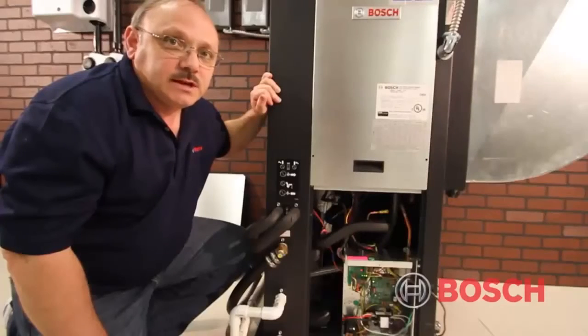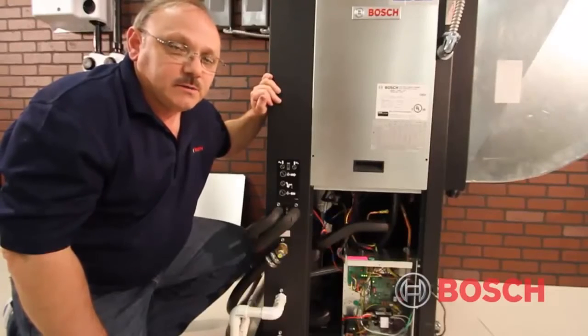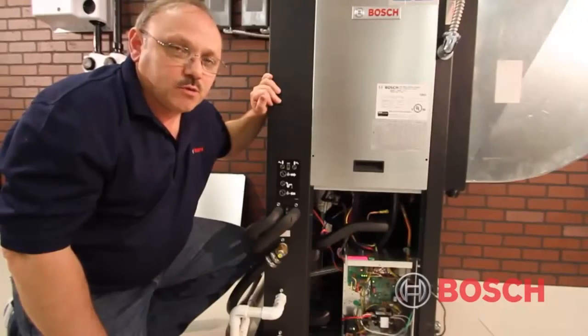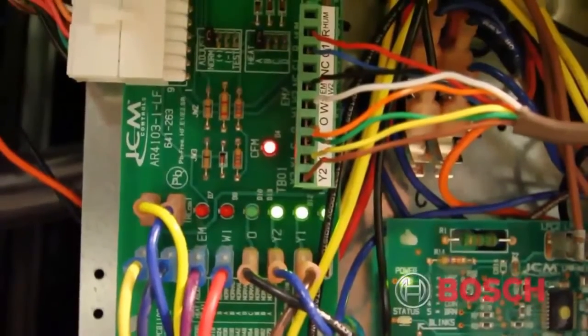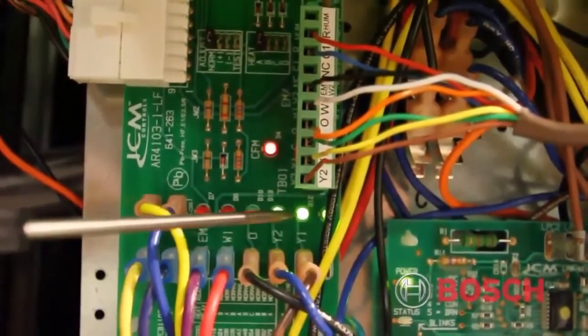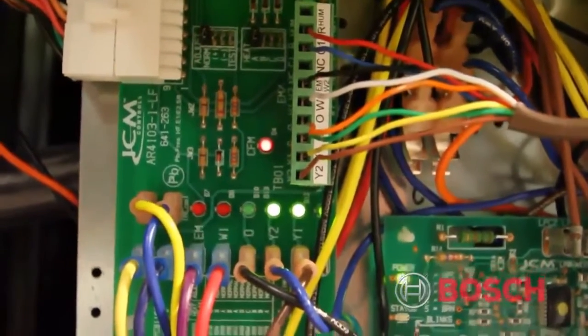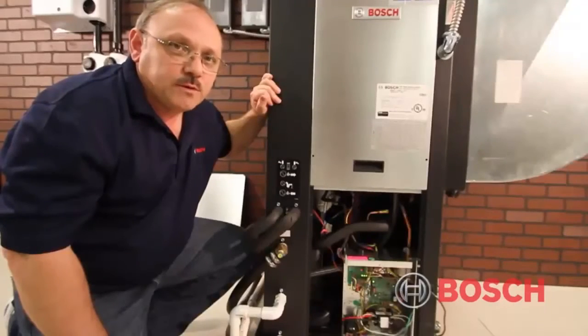As mentioned earlier, we like to check the waterside diagnostics in the second stage of operation. We're currently operating in the second stage cooling, and a simple way to verify that the thermostat is calling for the correct mode of operation is to look at the LEDs on the ECM control board. There are LEDs outside each terminal designation, whether it be G for fan, Y1 for first stage, Y2 for second stage, and O for reversing valve operation. We can quickly look at the lights to determine the mode of operation.